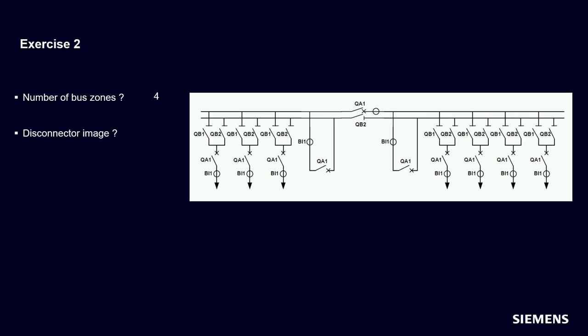Do we need a disconnector image? Once again, we have busbar disconnectors, so the feeder current could be assigned to different bus zones. It could be assigned to the upper busbar or to the lower busbar. So it's quite clear. We need a disconnector image here.